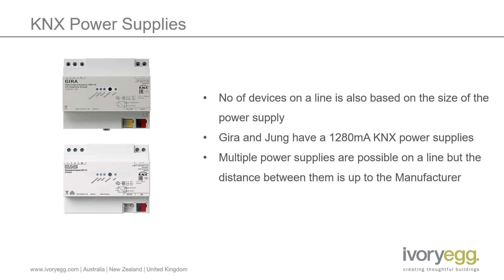These are pretty unique in the market. It is also possible to have some makes of power supply next to each other on the bus to increase the available current, but as a lot still require 200m separation, this needs to be checked carefully. Where you do need to add more power supplies, line repeaters can be used in the recognised way.